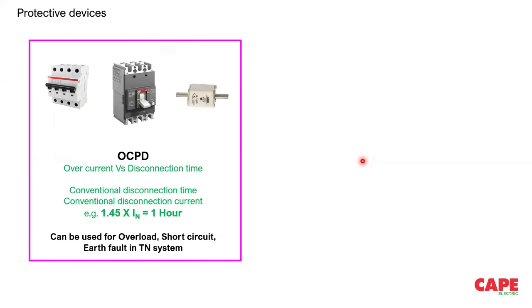The first category of protective device is called OCPD, overcurrent protective device. While selecting an OCPD in a particular circuit, we have to be very careful. We have to find out the overcurrent versus disconnection time requirement, and select the protective device appropriately. Always keep in mind that every OCPD has a conventional disconnection time and a conventional disconnection current. This means at a current of up to 1.45 times its rated current, the device can take up to 1 hour to trip. Today's devices are faster.